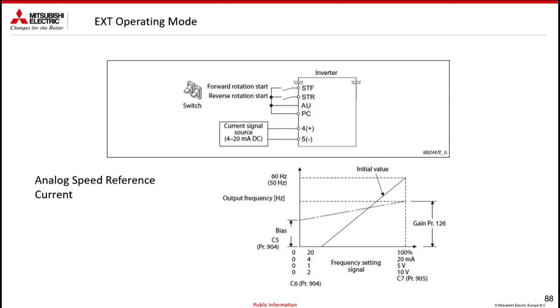Another example is with the analog input 4. As you can see, the AU signal is closed, which on an inverter FRD or FRA, as I said, I sacrifice an input to give the AU function, while on an FRA or FRF 800, it is already present. So I close such contact, I give the sense of rotation command, and I provide a signal that starts from 4 to 20 milliampere, which again is 100% calibrable, and I can define the maximum and minimum frequency as I want.